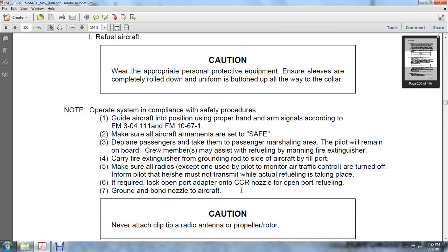Crew members may assist with the refueling, manning the fire extinguisher, carrying it from the ground rod to the side of the aircraft by the fill port. Make sure all radios except the one used by the pilot to monitor air traffic control are turned off, and inform the pilot that he or she must not transmit while refueling is taking place. If required, lock the open port adapter onto the CCR nozzle for open port refueling.